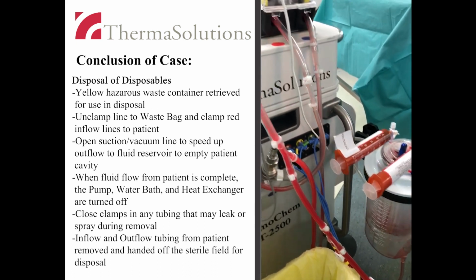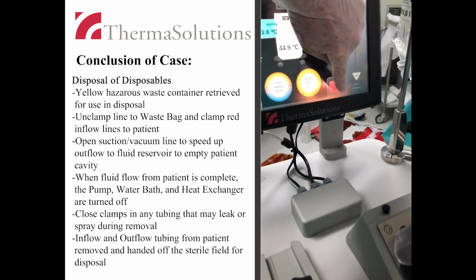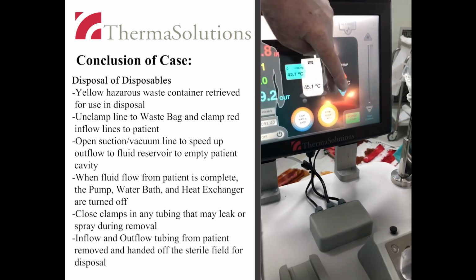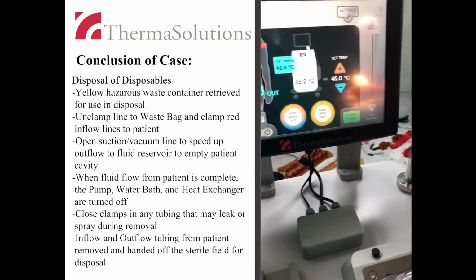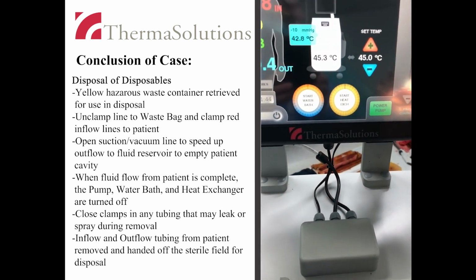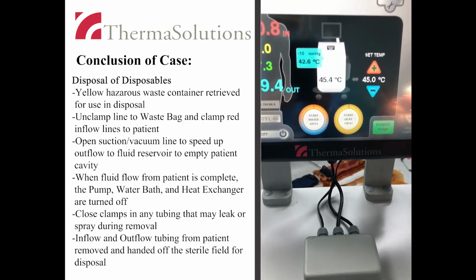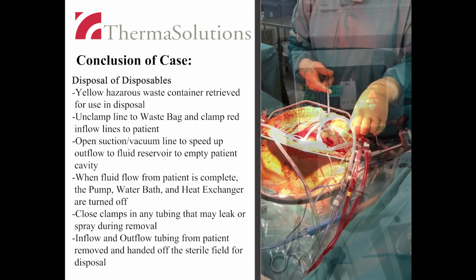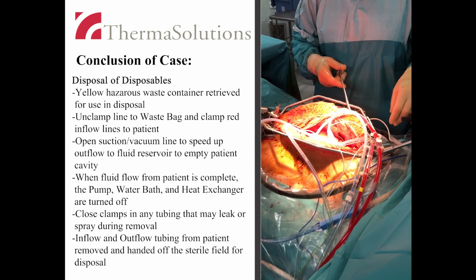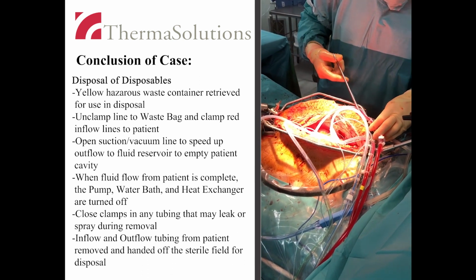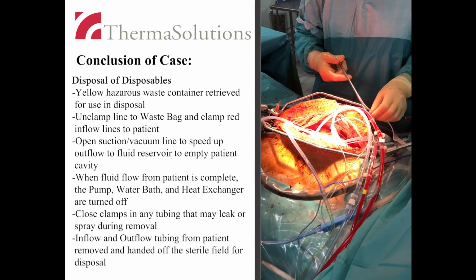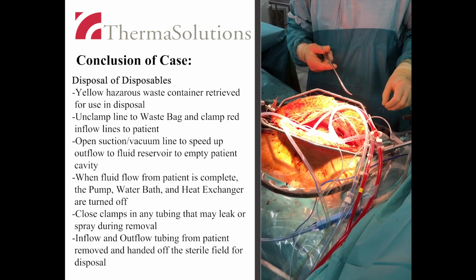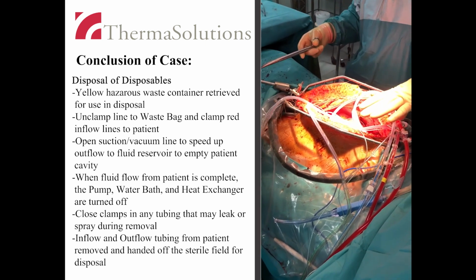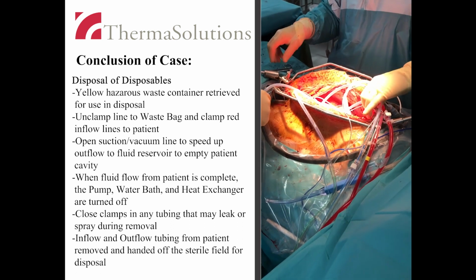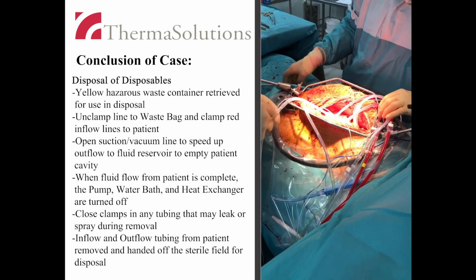When the fluid flow from the patient is complete, the roller pump is turned off. The heat exchanger and water bath are also turned off. Before disposal of the patient fluid system, close any clamp that may allow for fluids to leak or spray during removal. The inflow and outflow tubing from the patient is removed and handed off the sterile field for disposal.